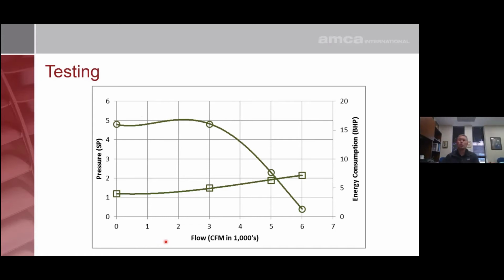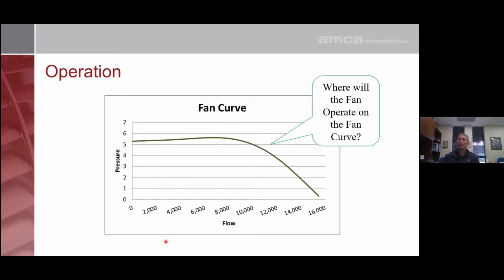Now, when a person comes to us and looks at a fan curve, I've oftentimes been asked, where's a fan going to operate on that curve? Well, as a fan manufacturer, we would state that a fan can operate at any point along that curve. There's an infinite number of points that a fan can operate at.